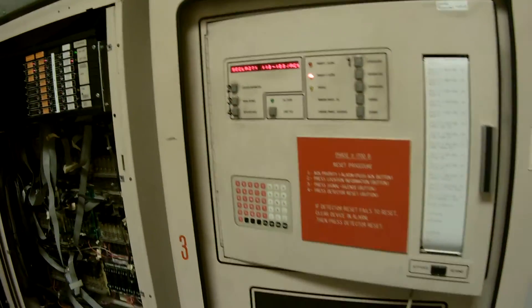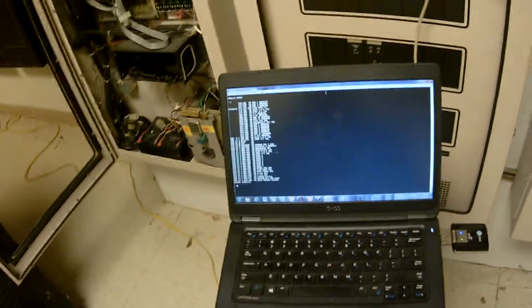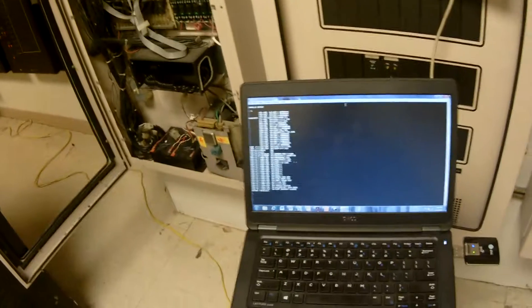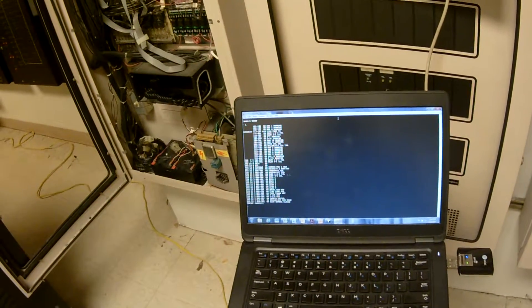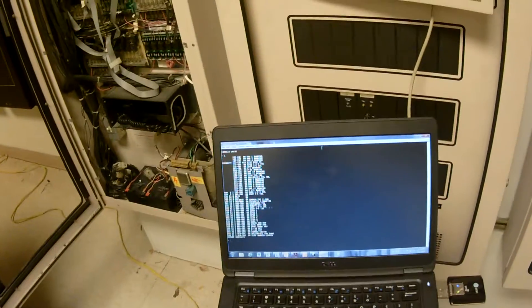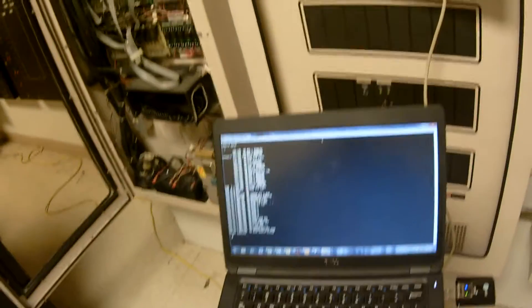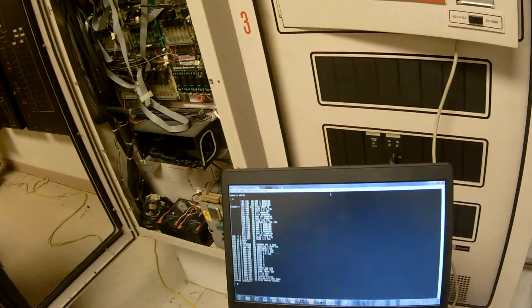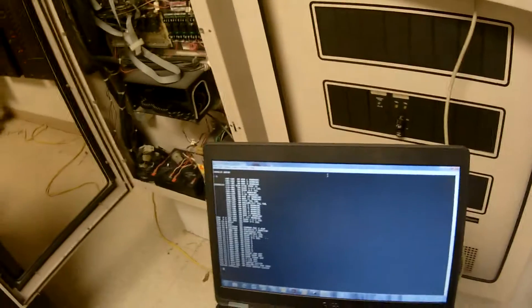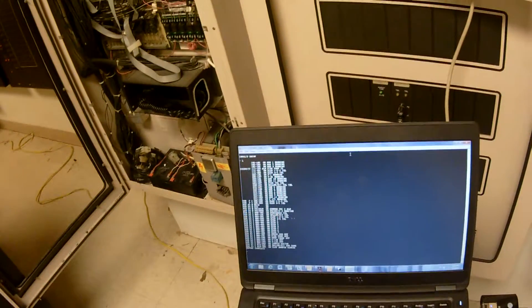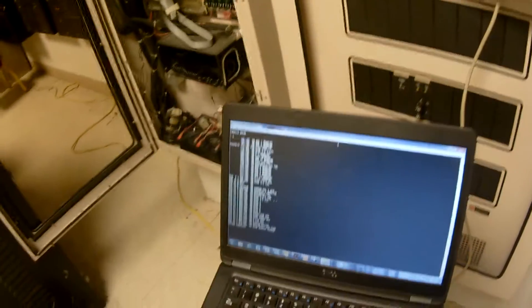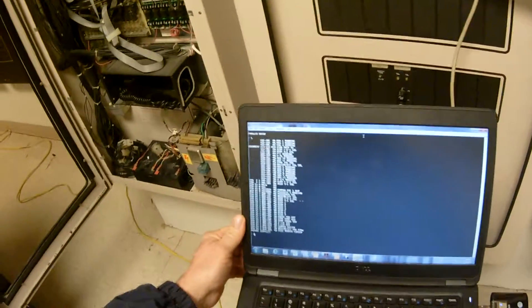And then from there, the system runs off of the RAM chip. So looking in this computer, basically I'm looking into this RAM chip. Anytime I want to make changes, I can make changes, and I'm just changing the RAM around. That's why these panels, if they were ever powered down and started back up, we would have to load our program back into it, or load our changes back into it that we made. And there was ways of backing up the changes.